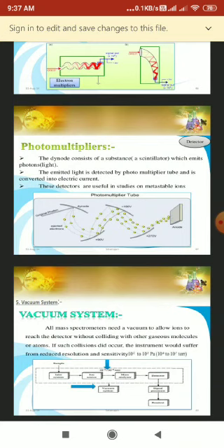Loss of ions from the sample may take place due to collision with molecules of atmospheric gases, resulting in a poor result.